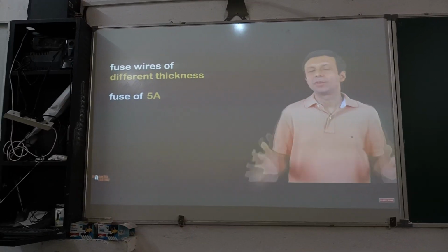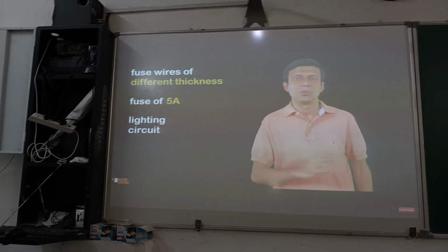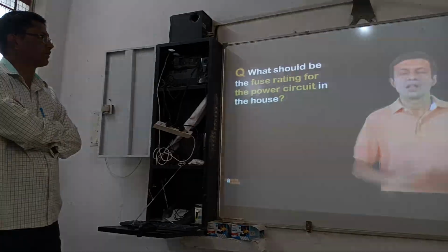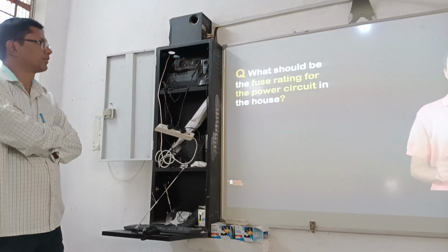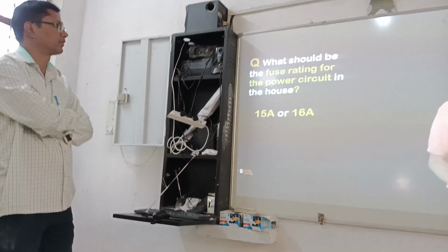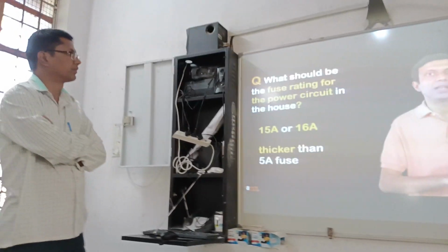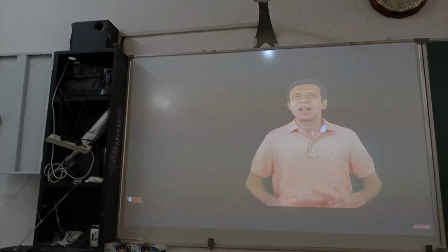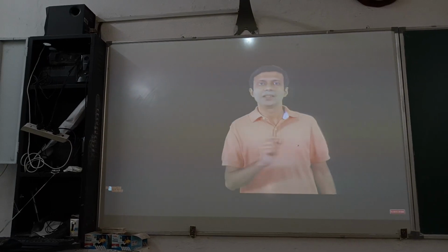A 5 ampere or a 6 ampere fuse is typically used for the lighting circuit in the house, where the maximum current should be around 5 ampere. Now what should be the fuse rating for the power circuit in the house? That's right, 15 ampere or a bit higher, say 16 ampere. So the fuse wire for the 15 ampere fuse will be thicker than the fuse wire for the 5 ampere fuse.